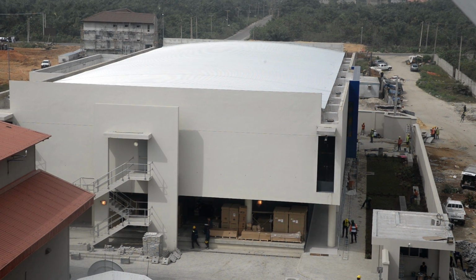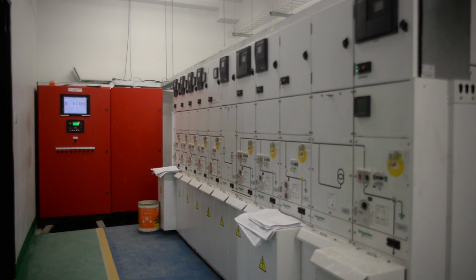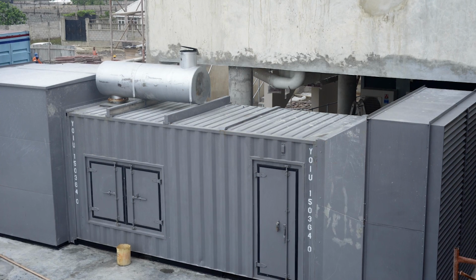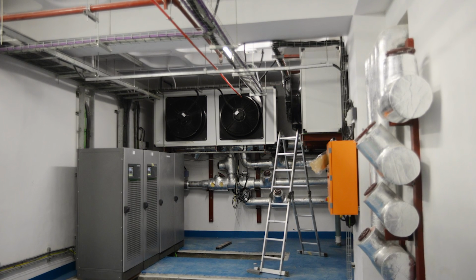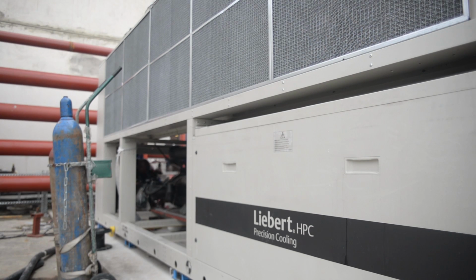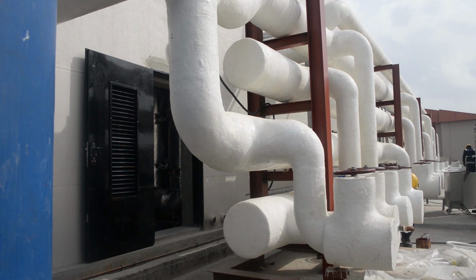For instance, in terms of the generator, our need is actually 3 of 1.25 MVA capacity. We've made provision for 6 because of the knowledge of our operating environment, and power is a challenge here. We have 4, 650 kilowatts of chillers.